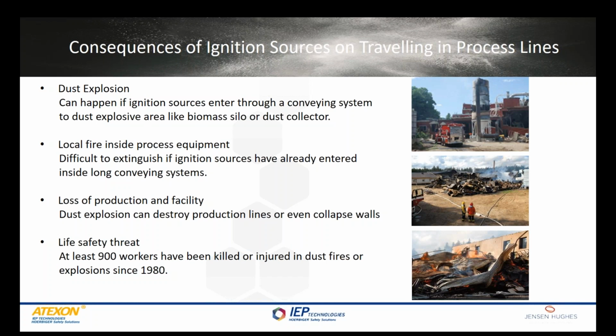Here we have some typical consequences listed of what can happen if ignition sources are not suppressed from production lines. Dust explosion is of course the most dangerous one because it can cause huge damages to production lines, facilities, and also to workers. The purpose of spark detection and extinguishing system is to suppress ignition sources before they enter the dust explosive area.